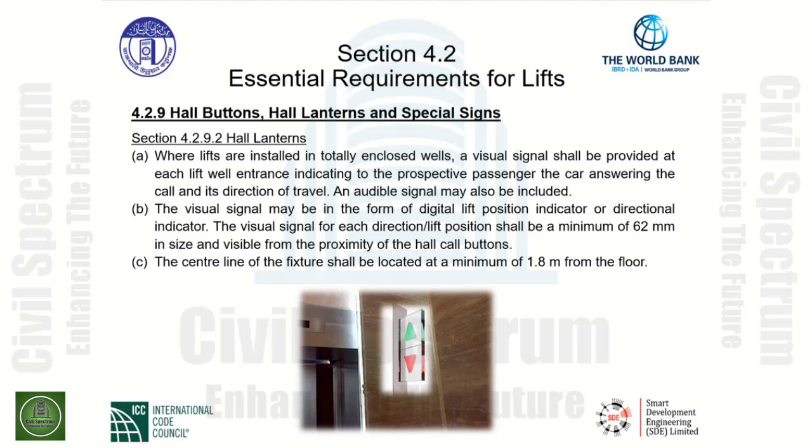As indicated in the picture below, we have a directional indicator that is indicated and so mounted above the 1.8 meter dimension from the floor, as well as providing illumination for people to see in the local area that is adjacent to the hall call buttons.